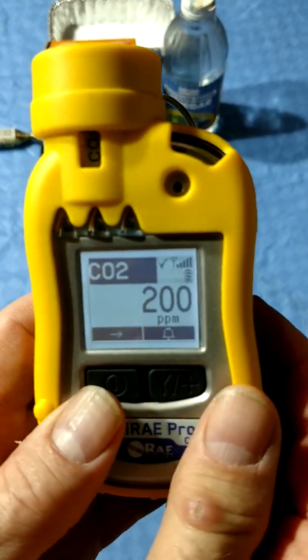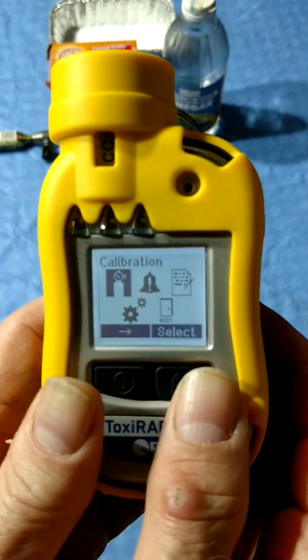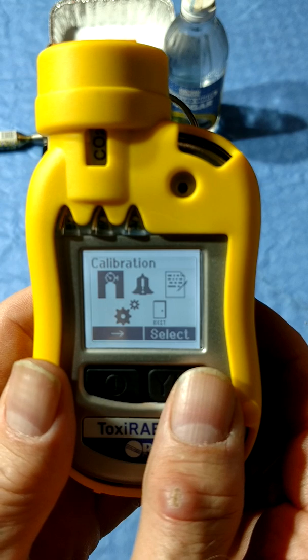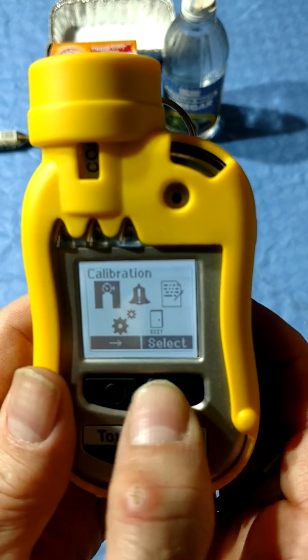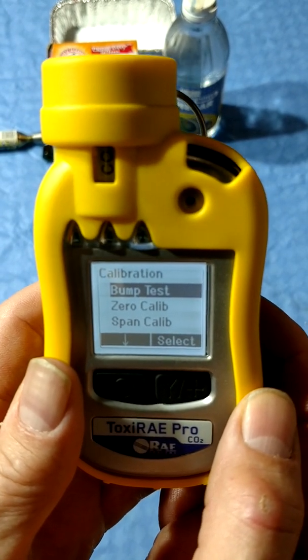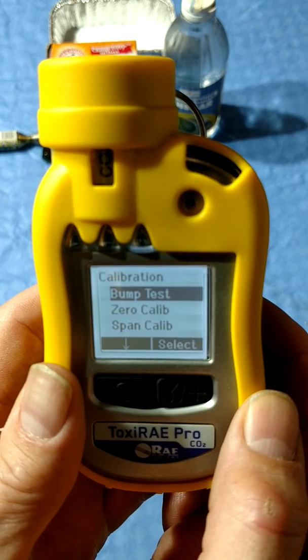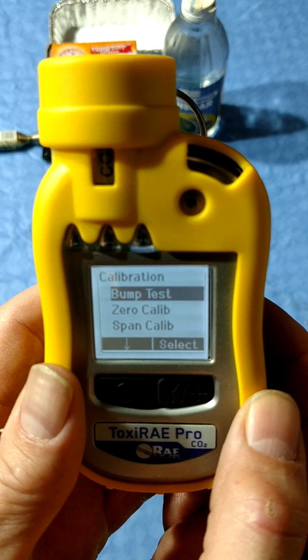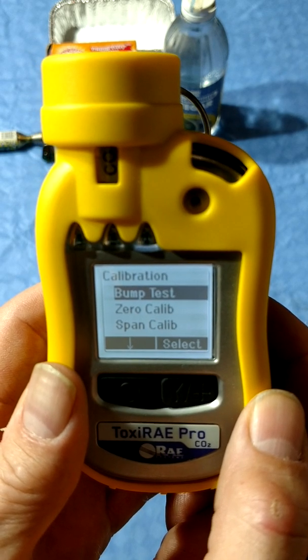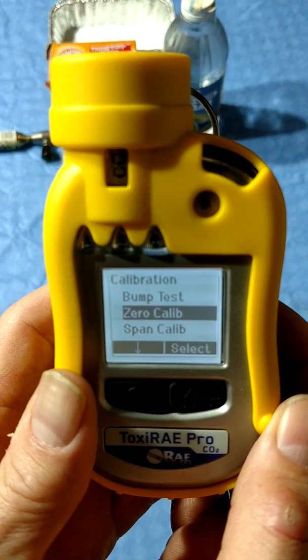To get to the programming menu, press and hold both buttons. Options are limited versus the MultiRAE. The calibration menu only has three options: bump, zero, and span cal. There is no fresh air cal. Outdoor air CO2 levels vary between 300 and 450 ppm. Indoor levels are typically 600 to 800 ppm. A zero cal is done with 100% nitrogen.